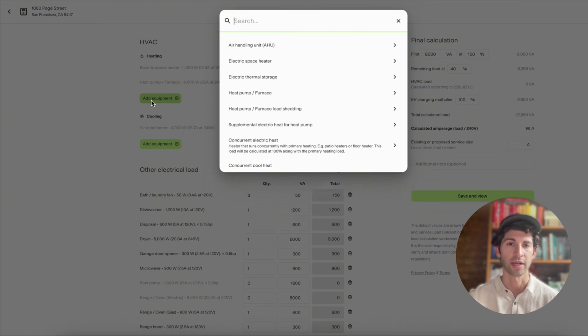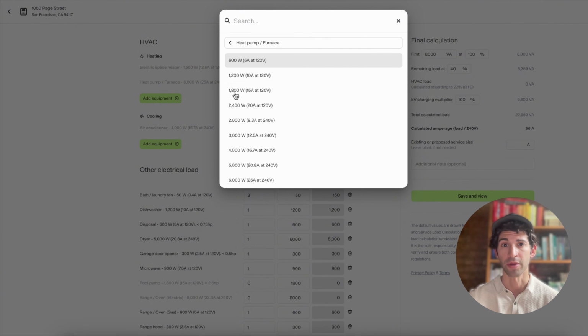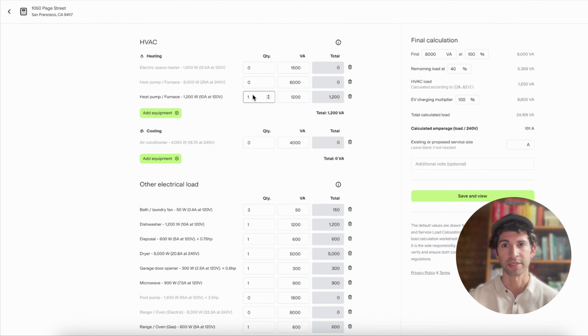In this case, the customer has a gas furnace with a big blower, which is rated at 10 amps. At 120 volts and at 10 amps, this is 1200 VA. Finally, we'll list out our other loads. According to 220.82, these are appliances that are fastened in place, ranges, wall-mounted ovens, and counter-mounted cooking units, clothes dryers that are not connected to the laundry branch circuit, and water heaters.